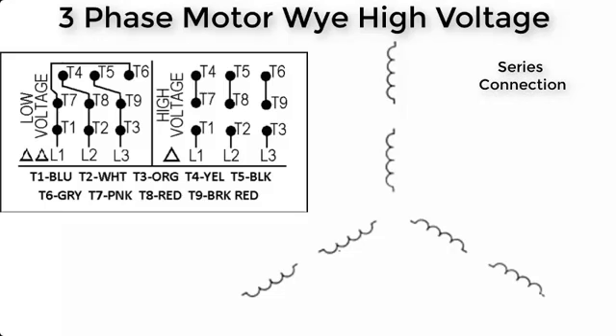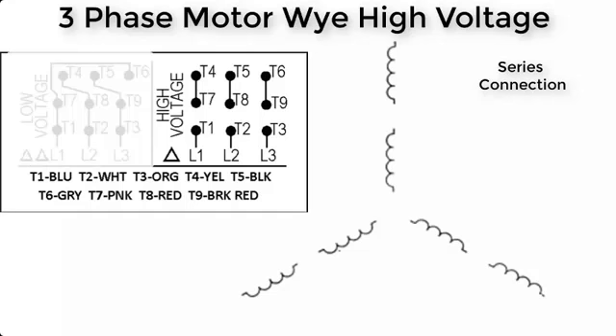This is going to be the series connection. So anything where it says higher voltage, then that's your series connection. If you wanted the higher voltage output on a transformer, you would connect up the windings in series. The higher voltage is coming in, so we're going to connect all of these windings up in series. Now we can go through the labels on each of these.